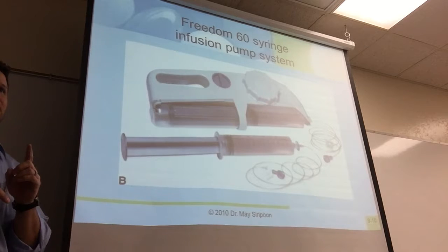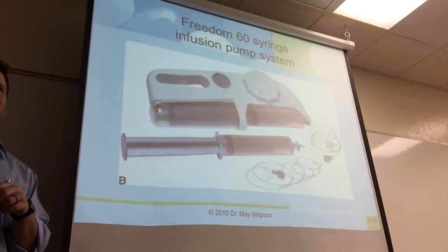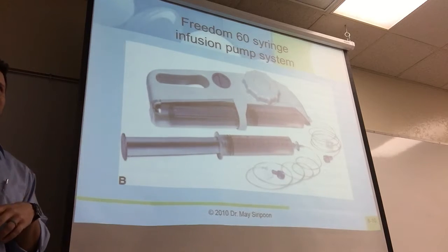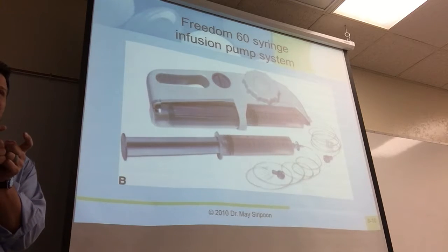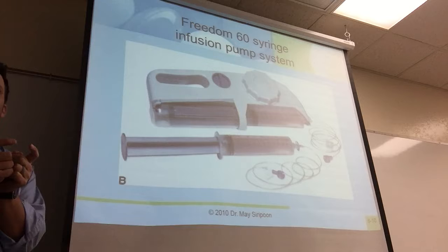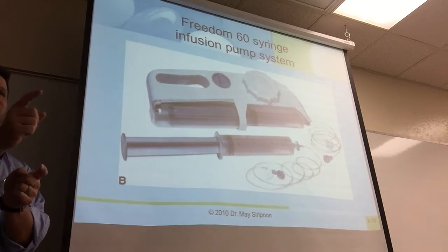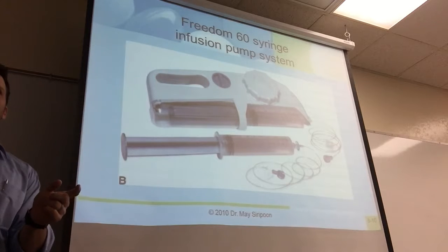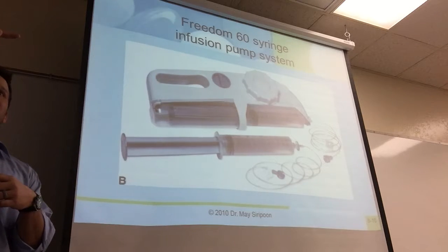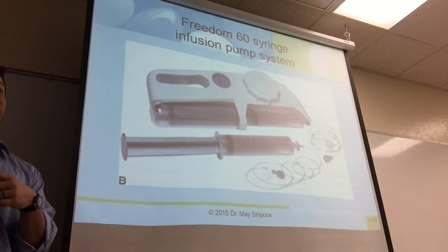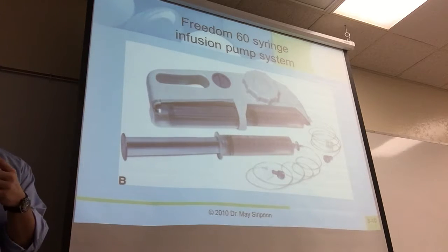Is it Baxter, Terumo, or some other brand? And then I put Terumo, and then that little clasp on it measures it and says, okay, you have a 30cc syringe. And then you say, is this a 30cc syringe? And you hit yes. And it automatically confirms it. So that way, it can use the plunger at the right rate to get the right mLs per hour based on the size of the plunger. Pretty cool.